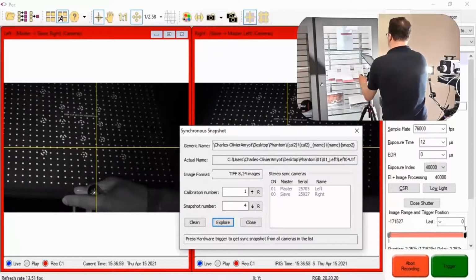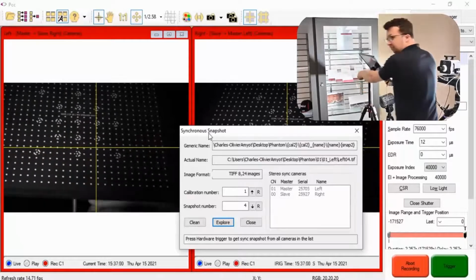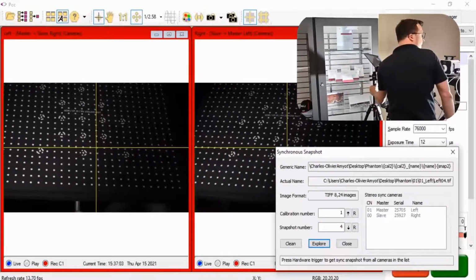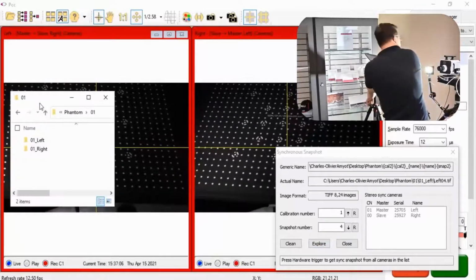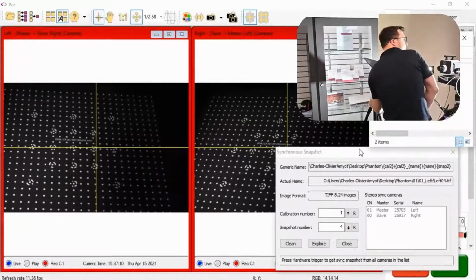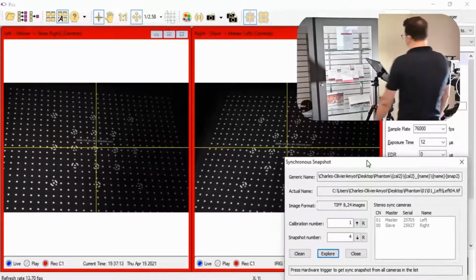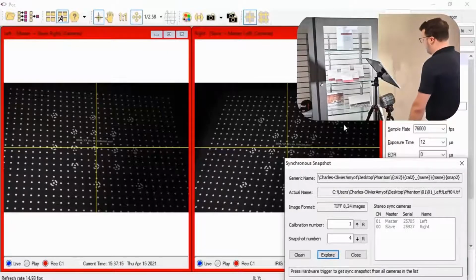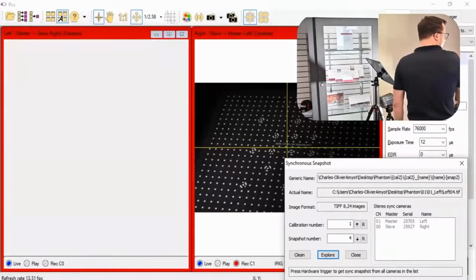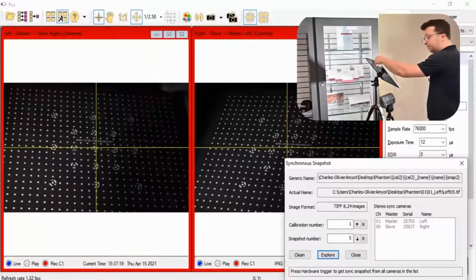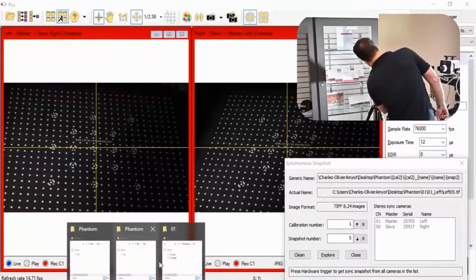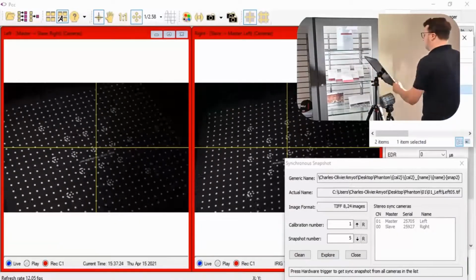Our next image is going to be at an angle to compensate for any lens distortion that we could experience during the test. I'm going to go a little lower in this case because I changed the angle. All right. And I'm still aiming my 2 cameras at the center of my field of view. Going to be image number 4. Image number 5 is going to be with a rotation of 180 degrees. All right.